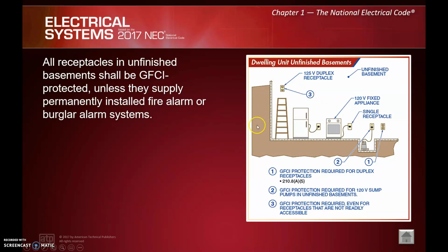So, ton of GFCI stuff here, right? They're really hitting it, right? So let's just hit a couple of these here. GFCI protection required for duplex receptacles. I like number 2 here. GFCI protection required for 120-volt sump pumps in unfinished basements. That's dwelling units. If you've ever done elevator pits, there's actually an exception to that. But for residences, we still need that GFCI protection.